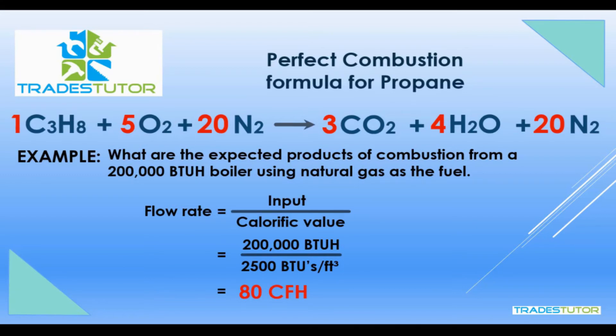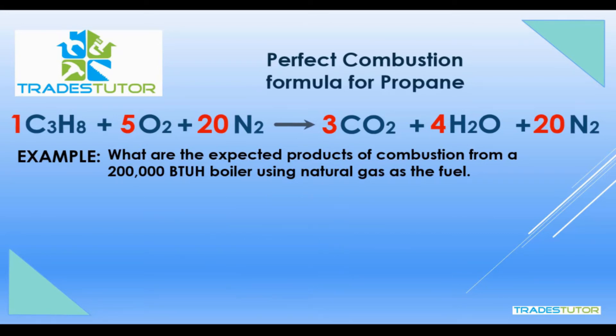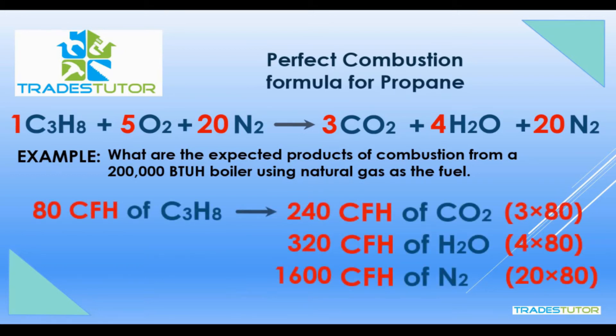Now we can use our ratio numbers to work with that. If you start with 80 cubic feet of propane and you get three times as much carbon dioxide, well, you get three times 80 — or 240 cubic feet. The water vapor is four times as much, or 320 cubic feet. And the nitrogen is 20 times as much, or 1,600 cubic feet. So that is the perfect combustion formula for propane, and we use that to calculate the products of combustion.